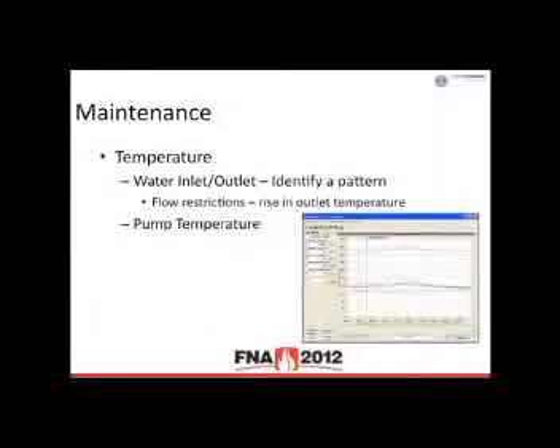Temperature is a big one. If I look at my water inlet and my outlet, I can identify a pattern. It's very easy to monitor some of these - these are just simple data points, and you can alarm on this too. So if you know that I'm trending in one direction or another, you can then identify that maybe my pump's getting too hot, or maybe I have scaling buildup in my cooling jacket.